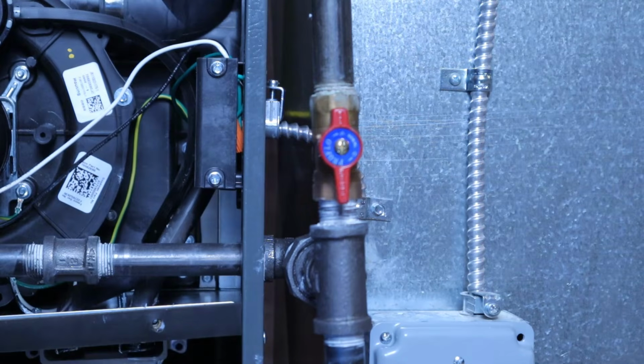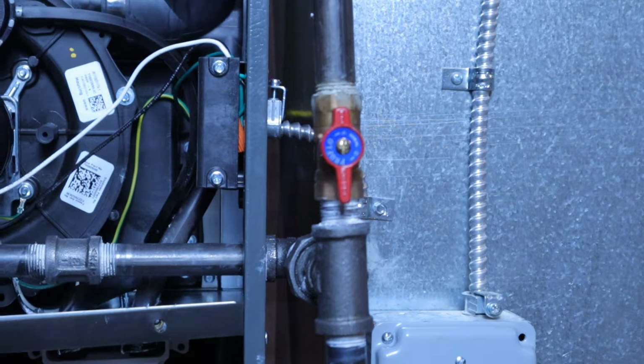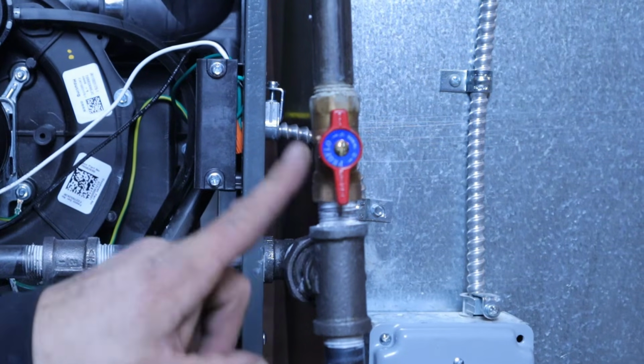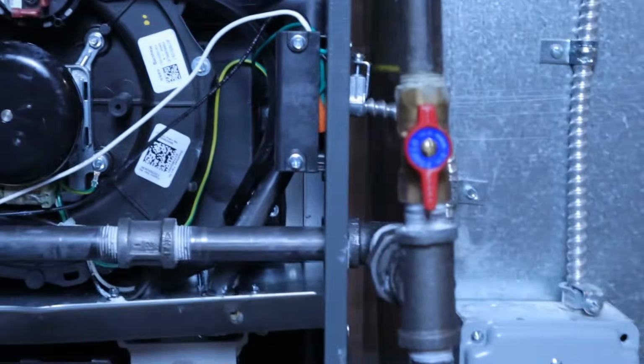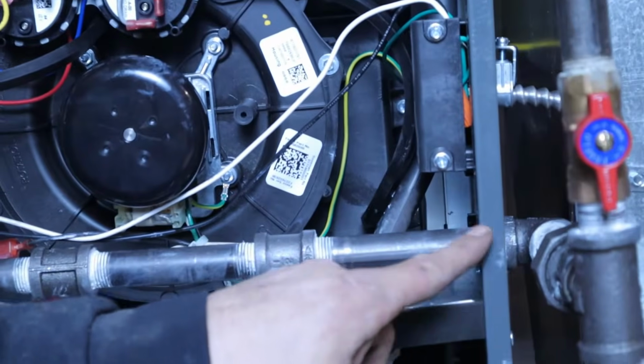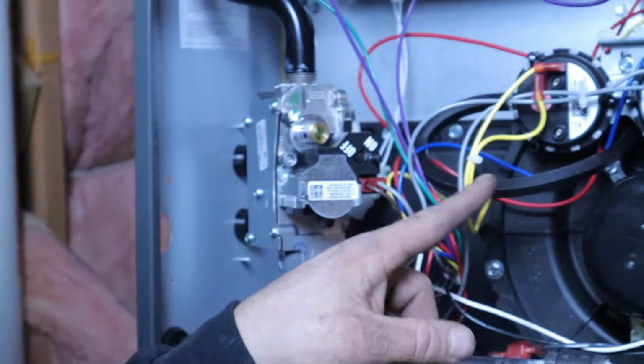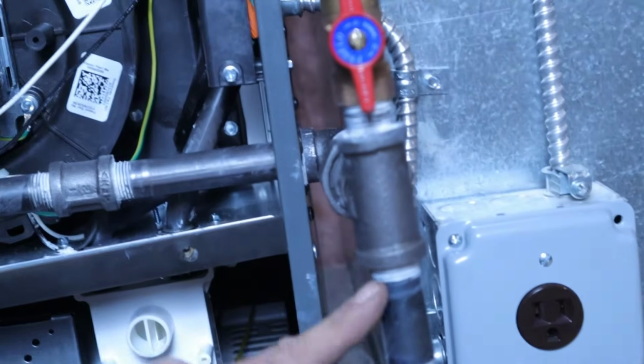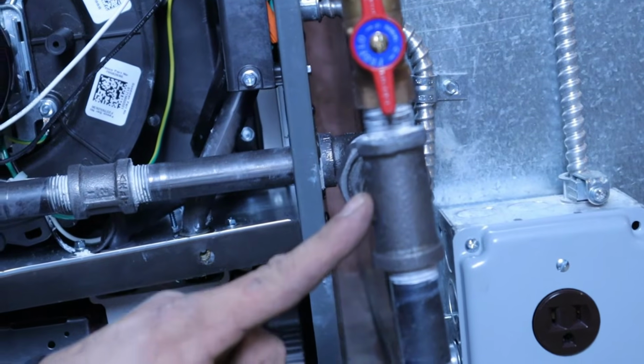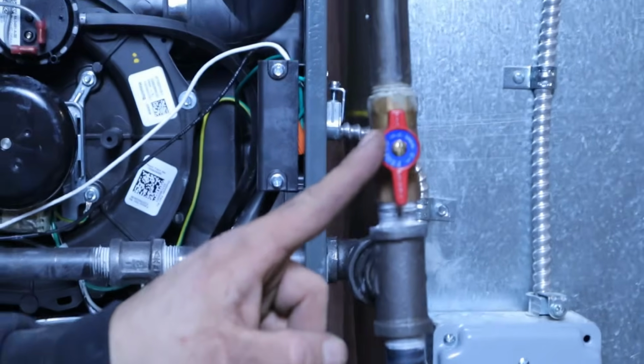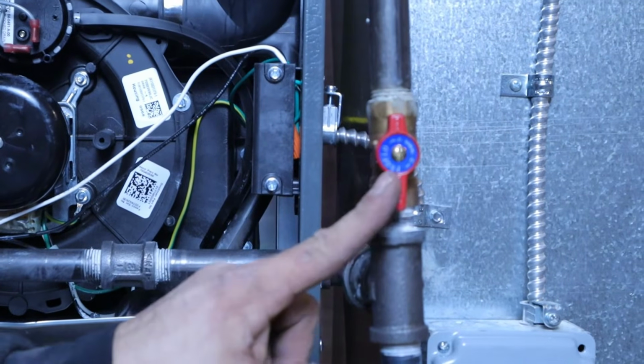So our electrical is done. The gas is already done as well. We have our shut-off valve here. We have the gas coming into the furnace, going to the gas valve, and we have a drip leg on here below a T. So when we finish the gas, what we do is we turn the gas on.